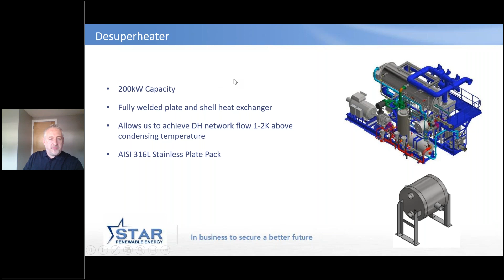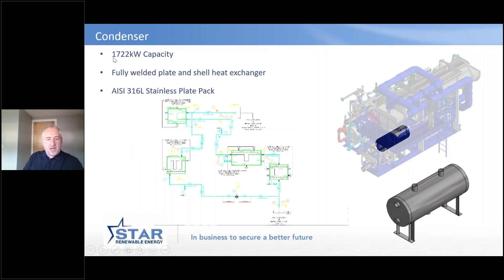So desuperheater, it's about 200 kilowatts out of 2,600. In terms of the condenser, it's about 1,800 out of the 2,600. So that's really the biggest chunk of the heat recovery. We can see in the subcooler, it's about 200 as well. And this is probably the one that features most in the next couple of slides as to why it's important. Obviously, we can adjust the temperature we flow forwards by managing the network better.